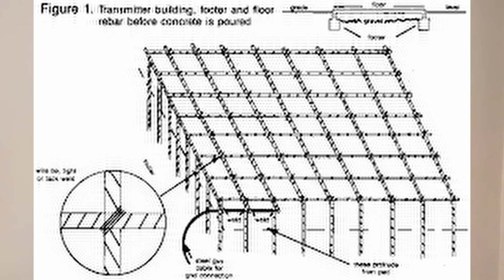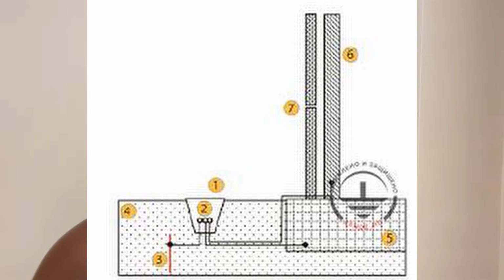The strongest earthing system uses the building foundation itself. This involves installing copper tape or a bare copper conductor laid continuously around the foundation perimeter. You then bond it to the steel reinforcement rebars of the foundation, as I said earlier, then fully encase the whole lot in concrete. This is the strongest earthing system. If you haven't done your foundation yet and you're watching this video, stop, go back, do this before you pour the concrete. You will not have any issues with the earthing.